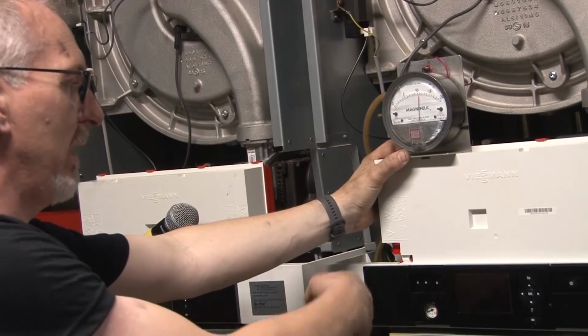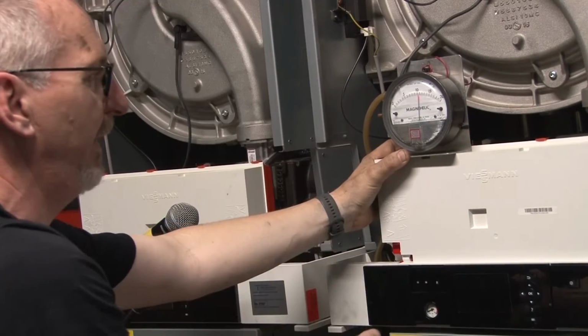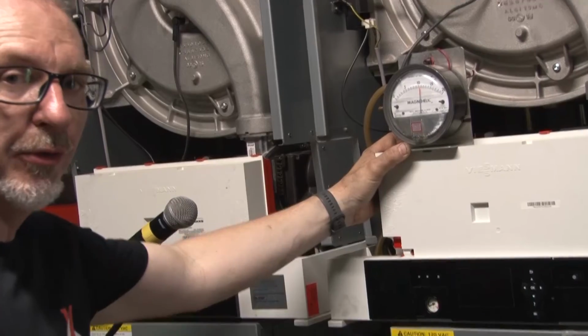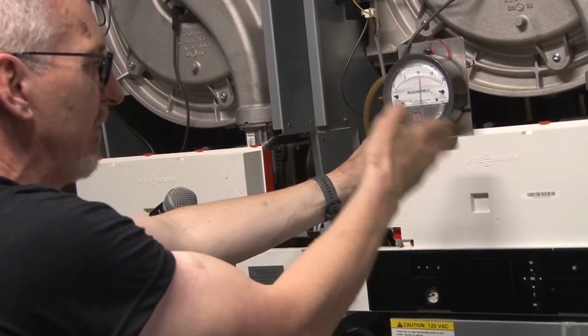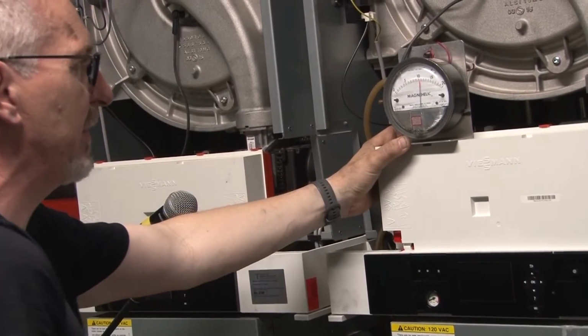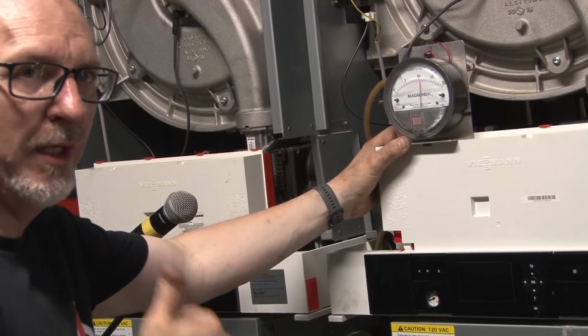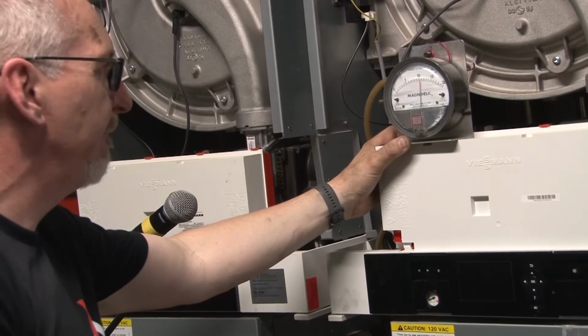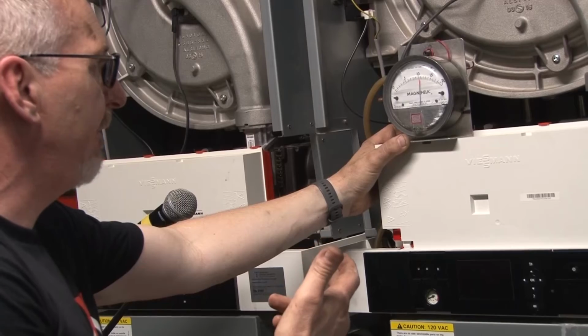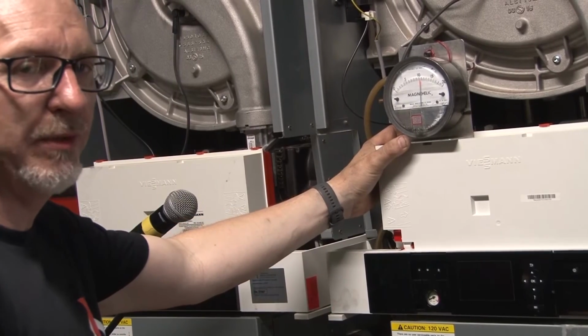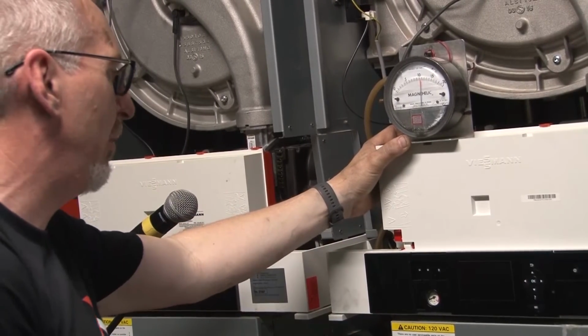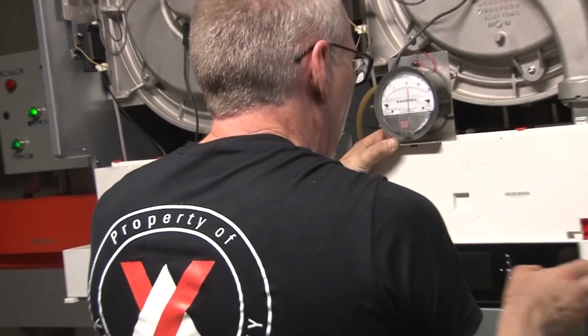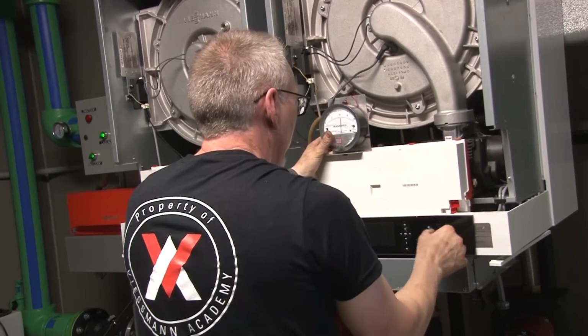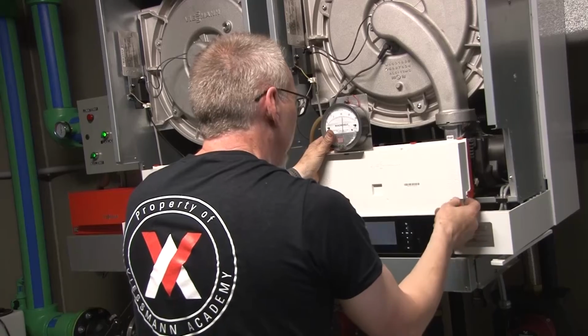So with lockup pressure on commercial boilers, it's like when we shear a flame, where does that gas pressure go? Does it bump up as a result of that flame shear above 14 inches? This one's stable, right back up to 11 inches. So we've got static at 11 inches, high fire about 8 inches, and then lockup was about 11 inches. So everything's safe to go on this boiler. We can basically now turn the boiler back on.